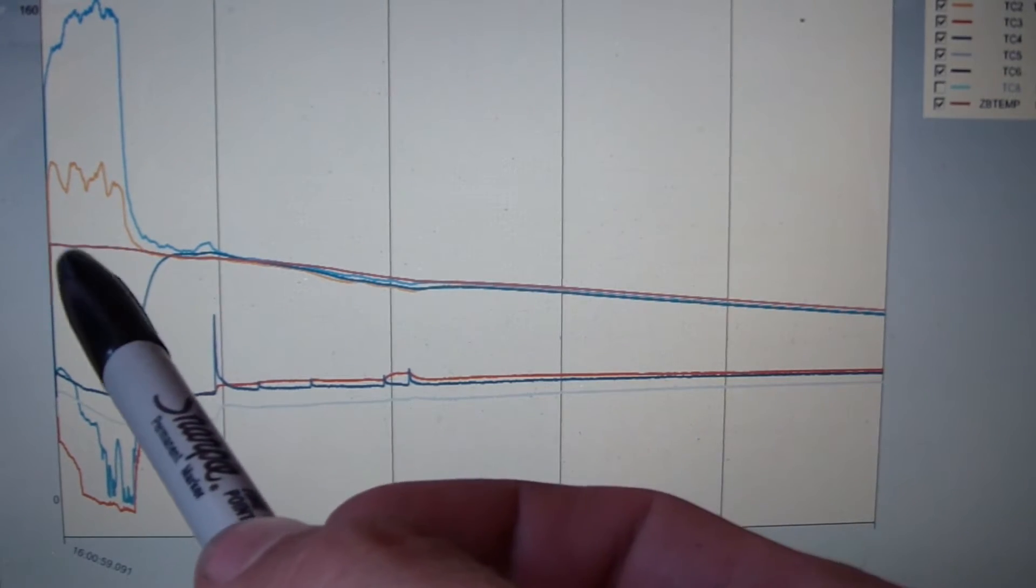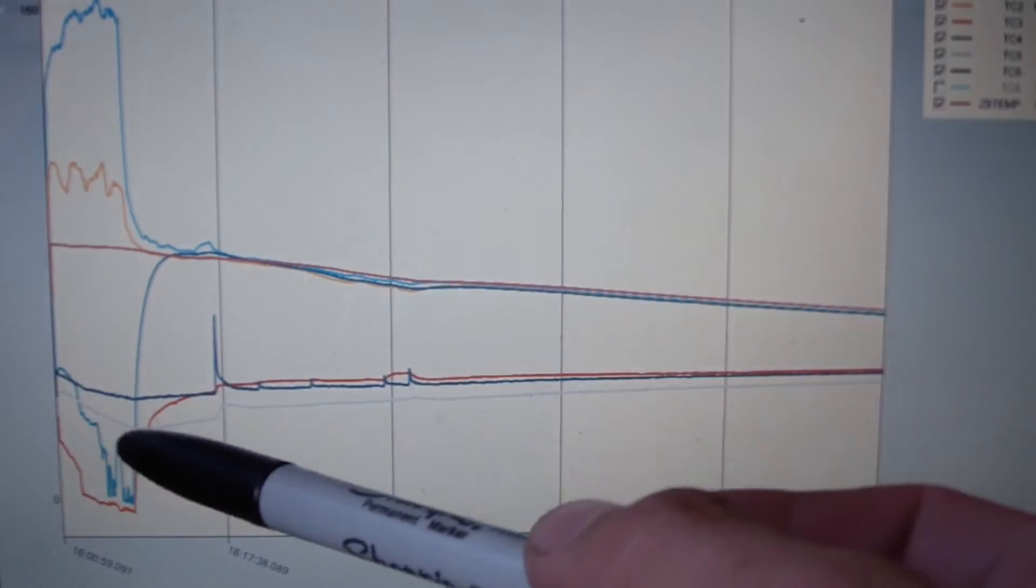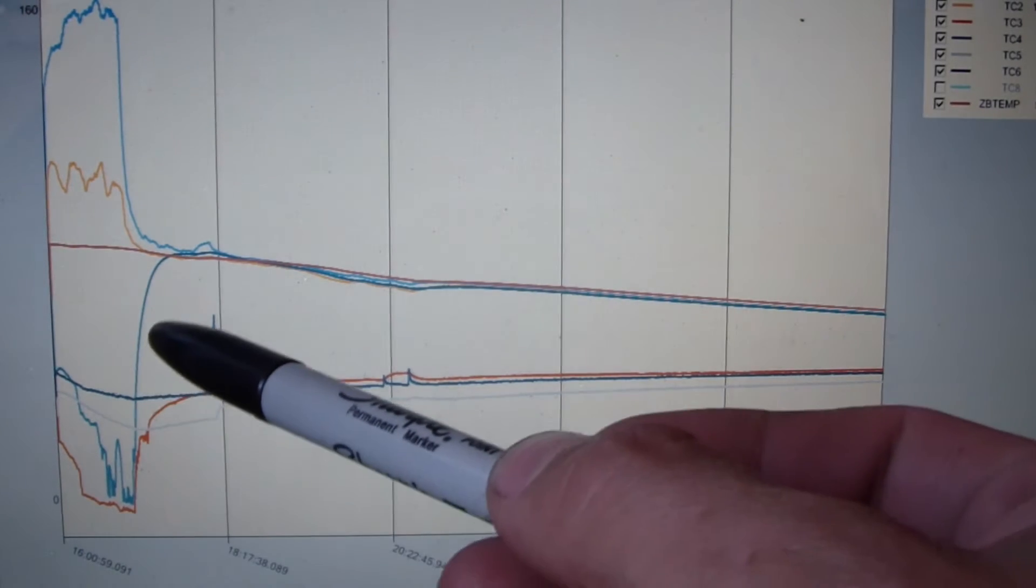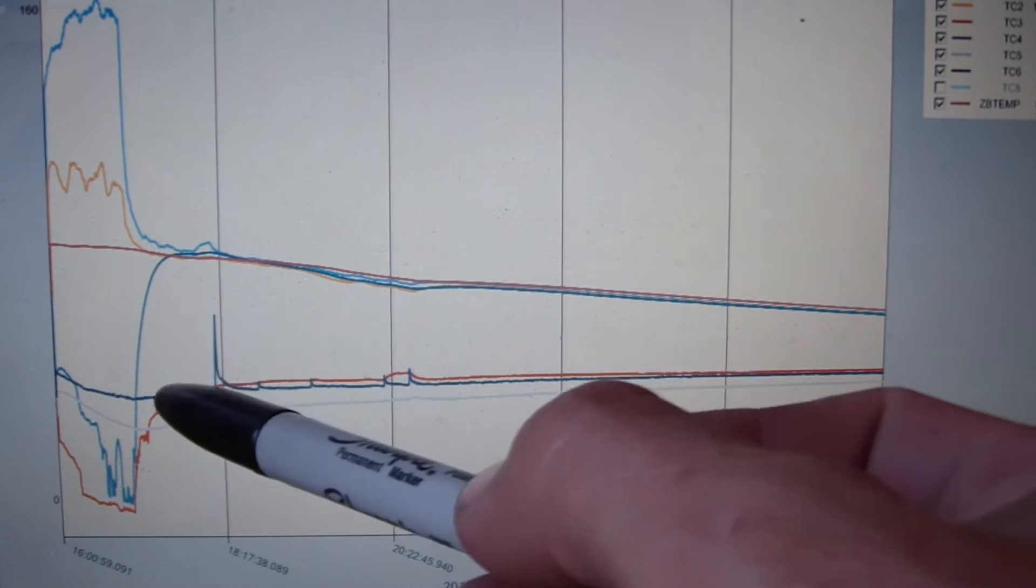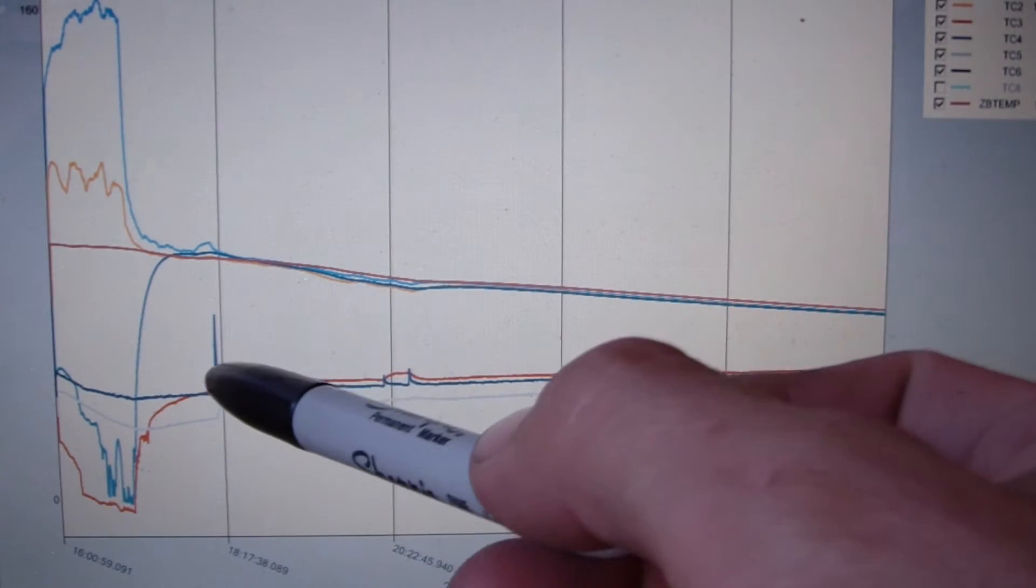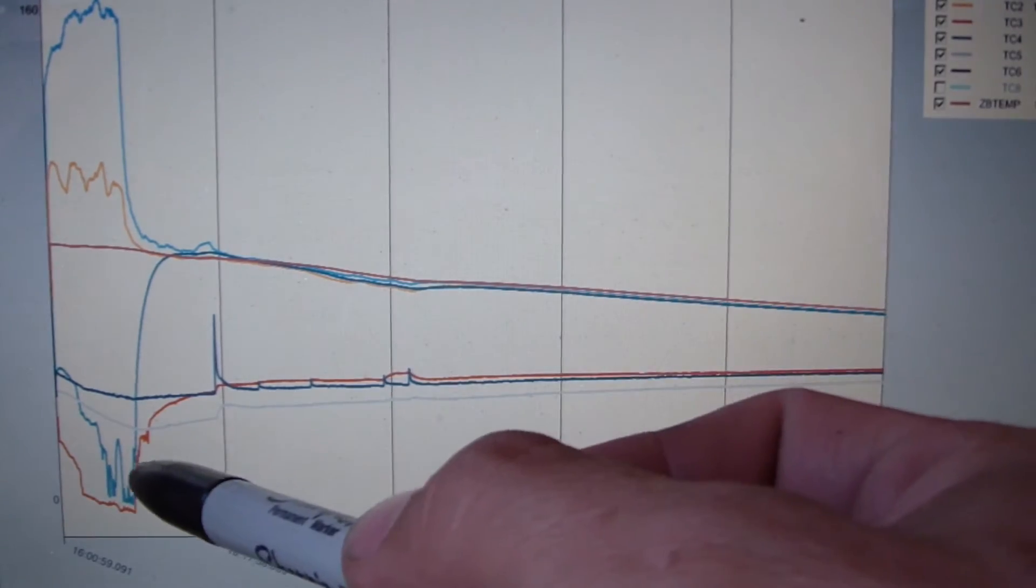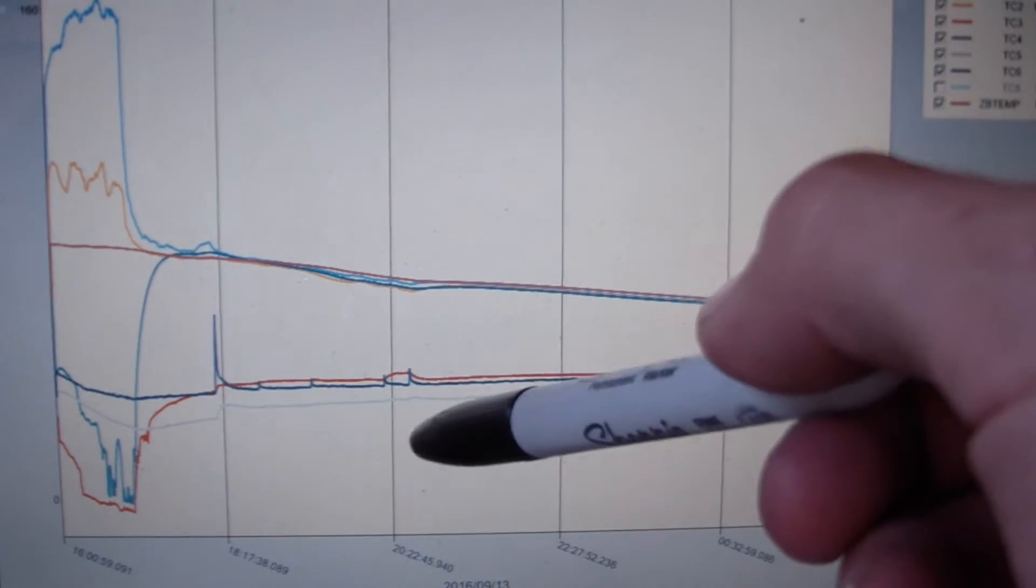Here's a shutdown right here and then the upward trend of the superheat. That large jump right there, that's the box temperature in the bottom. The superheat that's in the thermocouple in the box pretty closely corresponds. The temperature doesn't vary in there by just maybe a few degrees from spot to spot.